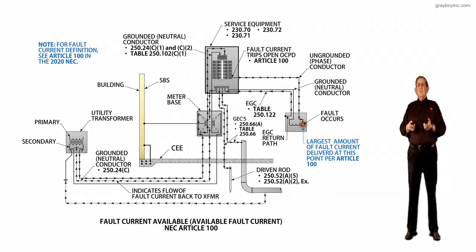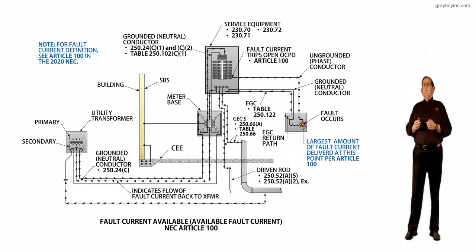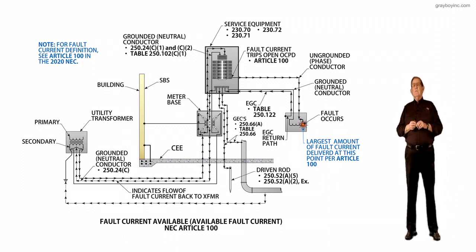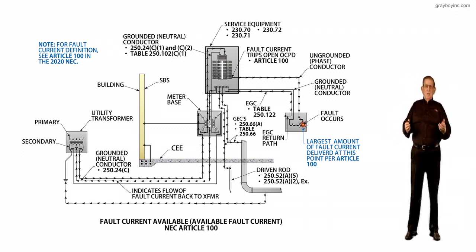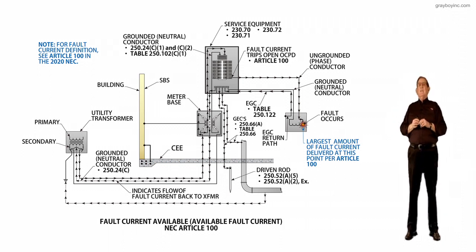But say that you had 10 kA breakers, then your short circuit current would be 8,500 amps there, then that 10 kA would interrupt it. That's what they're talking about, to make sure your breaker, 10 kA, 22 kA, 30 kA, whatever it is, is capable of interrupting the available short circuit current that could be delivered to that point.